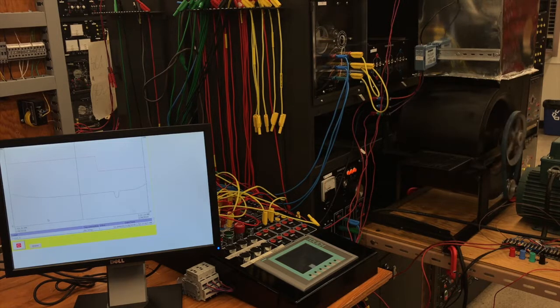Once we move to this screen, it shows the target temperature versus the actual air temp itself, and we choose a setting, and then the system will try and bring the actual air temp up to that chosen preset. The proportional controller we have will hunt a bit, but eventually it'll bring the measured temperature to the preset. We do this by varying the airspeed: when the temperature is close, we slow the fan down, and if it's quite a bit higher, then we speed it up, and if it drops below, then we'll stop the fan.